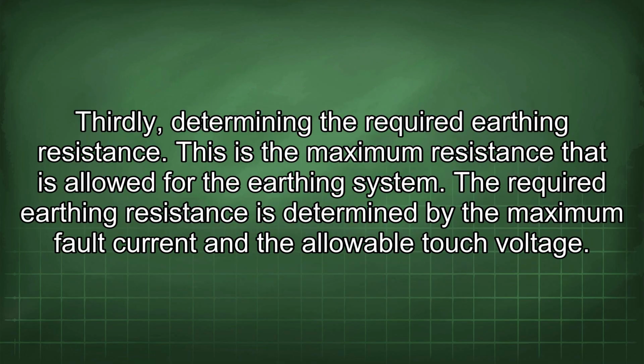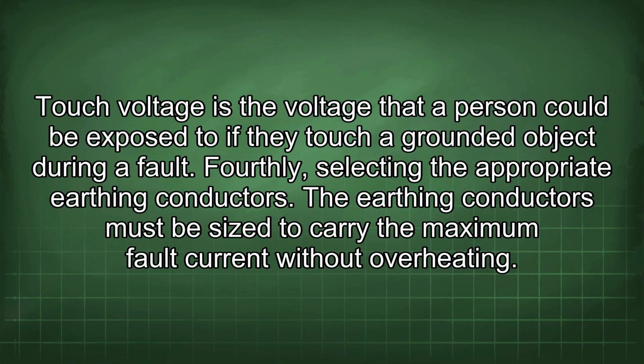Thirdly, determining the required earthing resistance. This is the maximum resistance that is allowed for the earthing system. The required earthing resistance is determined by the maximum fault current and the allowable touch voltage. Touch voltage is the voltage that a person could be exposed to if they touch a grounded object during a fault. Fourthly, selecting the appropriate earthing conductors.